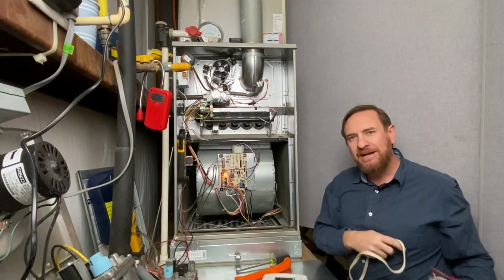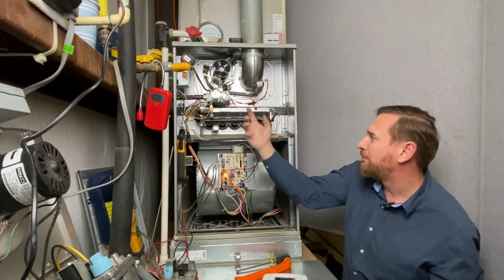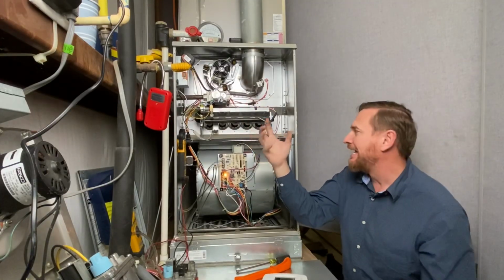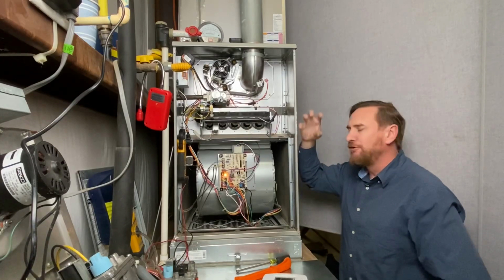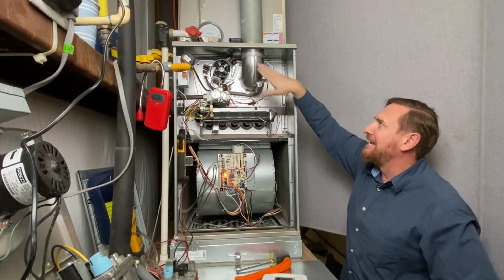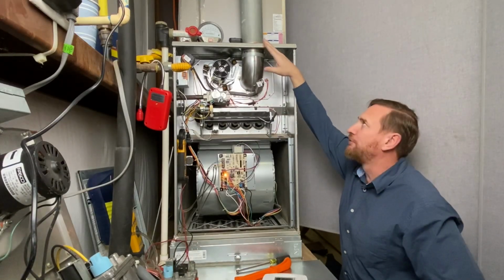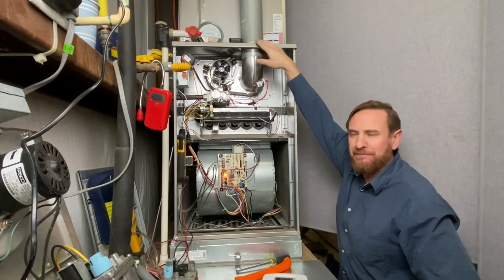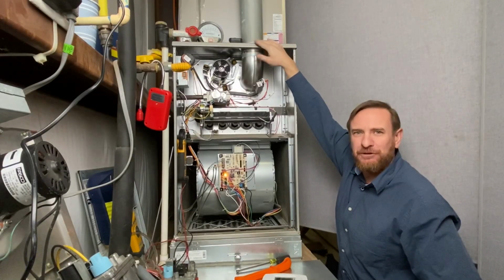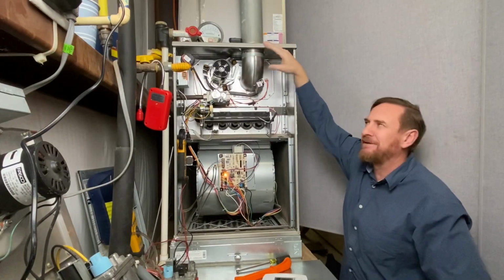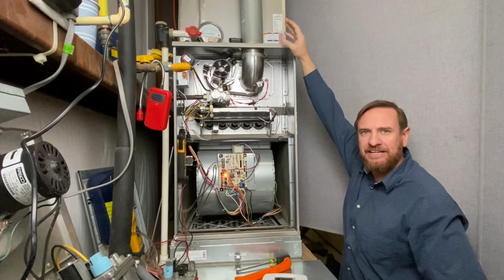Now what I want to point out to you is this inducer fan motor is pulling a draft through the heat exchanger. It's pulling the flames, the fuel mixture, through the heat exchanger, and it helps start or induce that draft through the flue pipe up here. But what's important is this flue pipe is a negative pressure flue pipe. It's still relying on natural draft to carry it out.